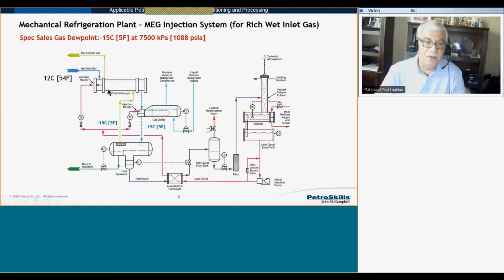an approach temperature of about 9 degrees Fahrenheit, which establishes the temperature here to be 45 degrees Fahrenheit, 7 degrees C. The approach temperature of 9 degrees means subtracting 9 degrees Fahrenheit from 54, and I end up with 45 degrees. And this approach temperature has economic impact on my process. So let's follow the process flow diagram, then I focus on the mechanical refrigeration part.